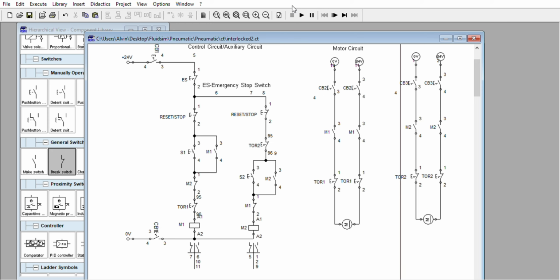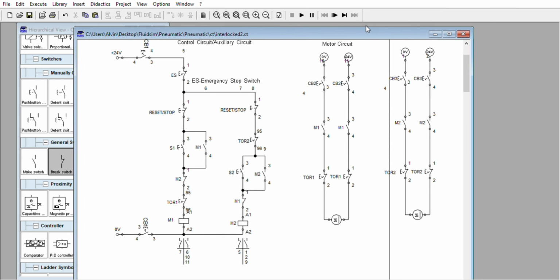Turn off the circuit, find the trouble of the motor, what causes the overcurrent. Maybe bearing, mechanical, stuck mechanical load, 3-phase, single phasing conditions, one phase is busted. You are going to find first the trouble before turning on the overload relay again.